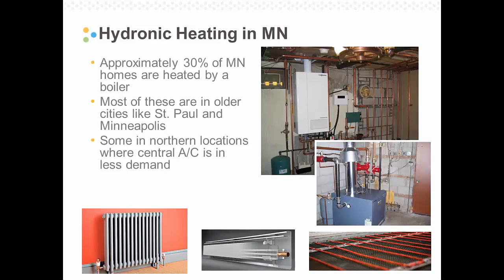Here are a couple stats about hydronic heating in Minnesota. Most of the heating systems in Minnesota are forced air systems. However, about 30% are heated by a boiler. Most of these are going to be in the older cities like St. Paul, Minneapolis. However, there's a fair portion in the northern locations of Minnesota where air conditioning is in less demand.